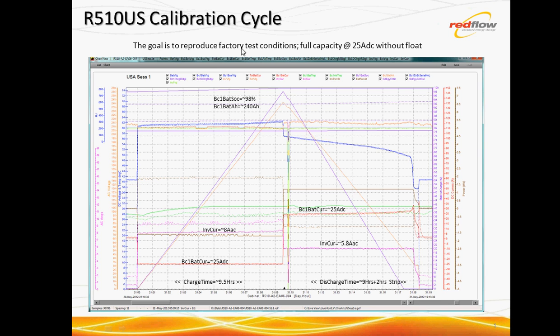The goal is to reproduce factory test conditions. That is a full capacity cycle at a nominal 25 amp DC charge and discharge without the hiatus of a float stage. So between the charge and the discharge, no gap there.